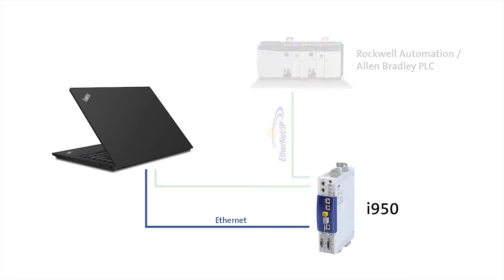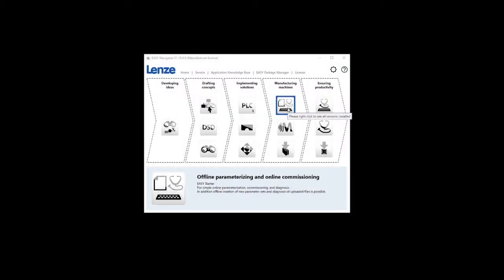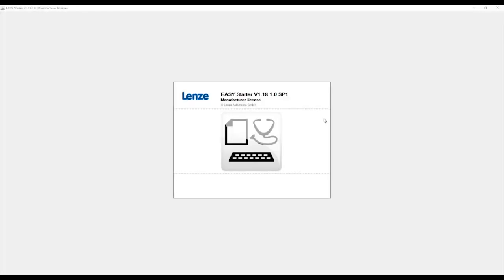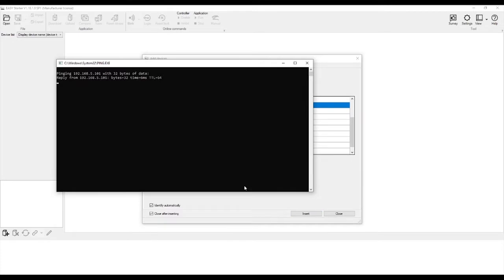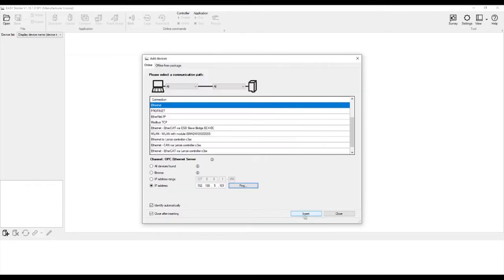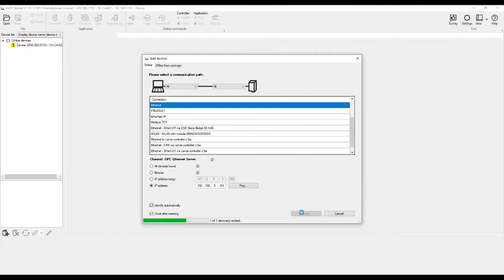Let's start off by connecting an Ethernet cable to the engineering port of the i950 to your computer. Open up Easy Navigator and click on Easy Starter under the Manufacturing Machines section. Make sure you have the Ethernet option selected for your connection type. Then ping your device to verify it is connected to your computer, then click Insert to go online with your device.